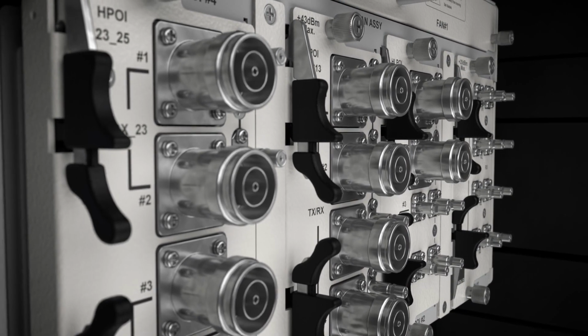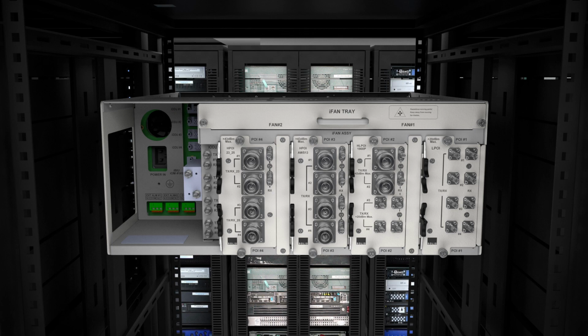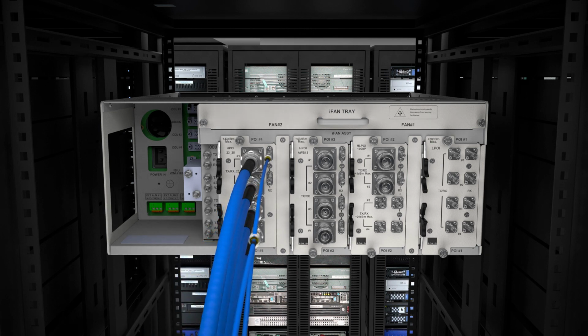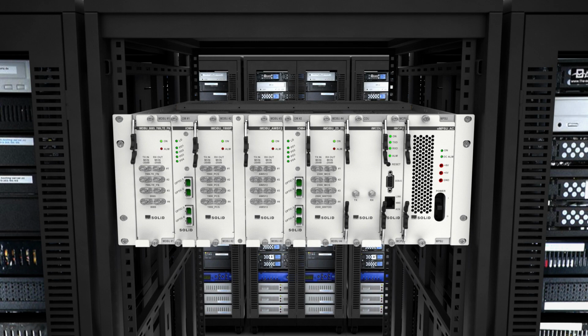Because they integrate with the iBIU, they significantly reduce the total amount of headend rack space versus other solutions. The POIs are available in high power, low power, and hybrid high and low power models. Up to 16 mobile network services may connect to the iBIU using either duplex or simplex cabling. The iBIU may be configured as a main or secondary unit.